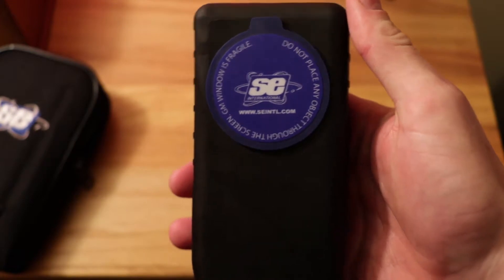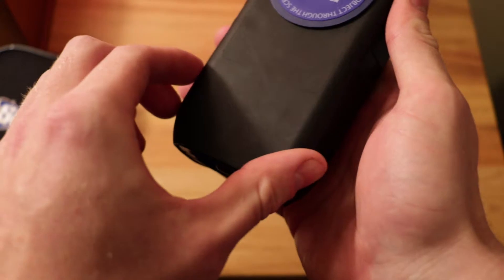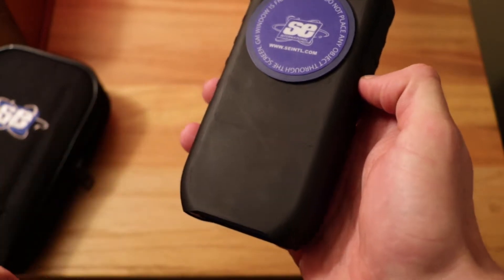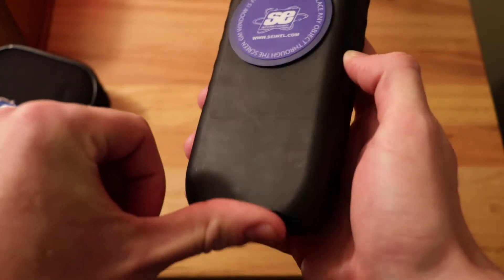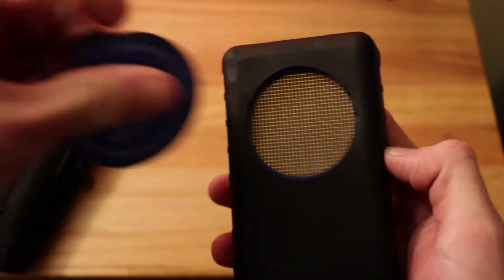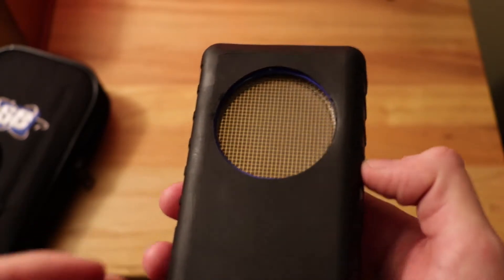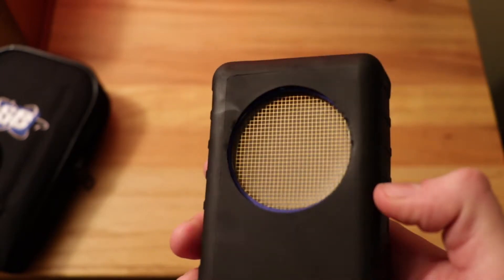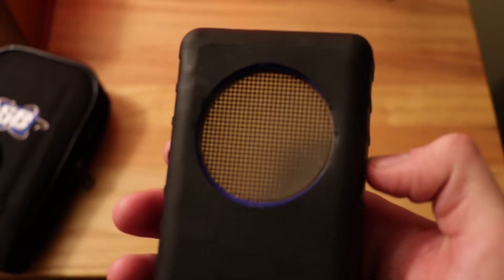On the back — I'm not going to take the Xtreme Boot off. The only thing on the back that's missing is the battery case, which takes two AA batteries. There's a little case that slides right out and clicks right in on the bottom. There's also a dust cover on the back. This is a pancake-type probe, so it can detect alpha, beta, gamma, and x-ray. It's really good at detecting lower levels because of the size of it — 45 millimeters across, or 1.77 inches.